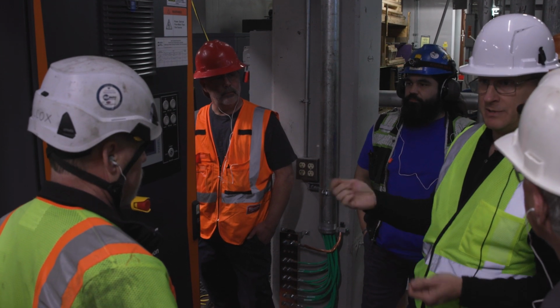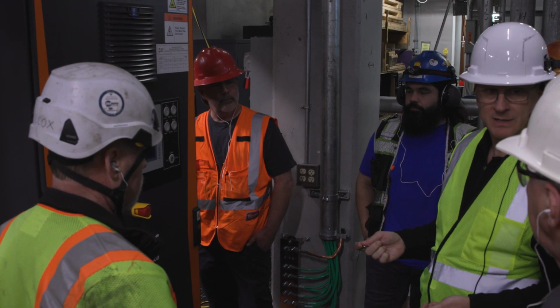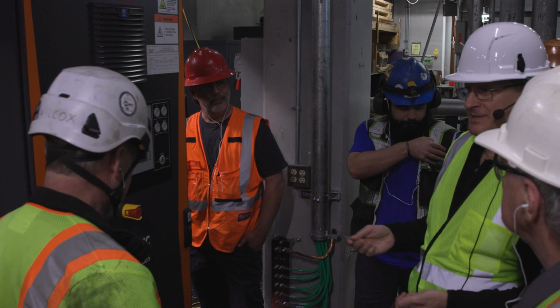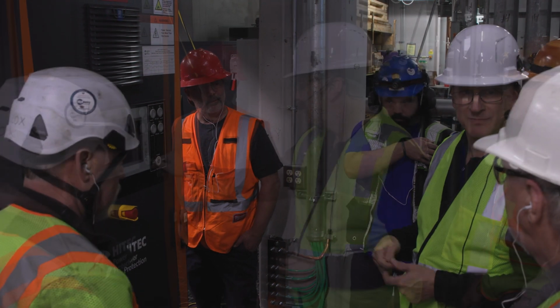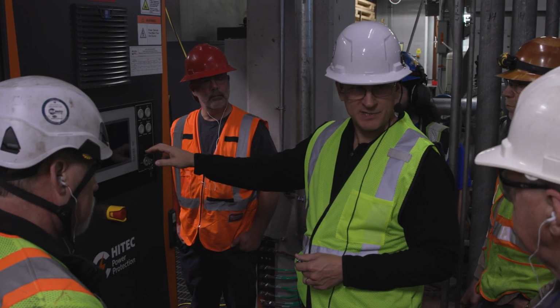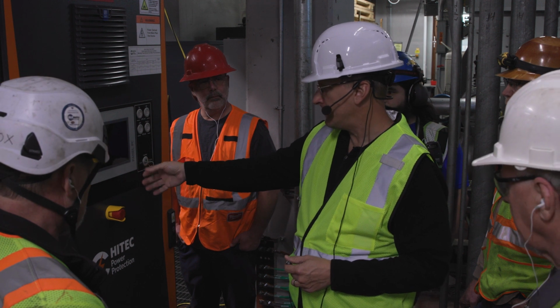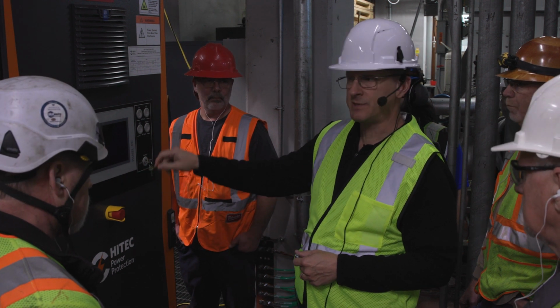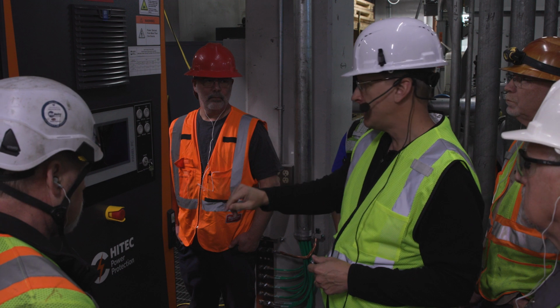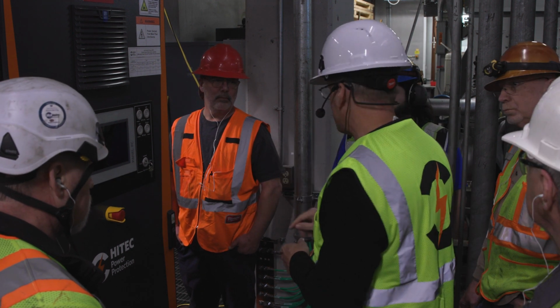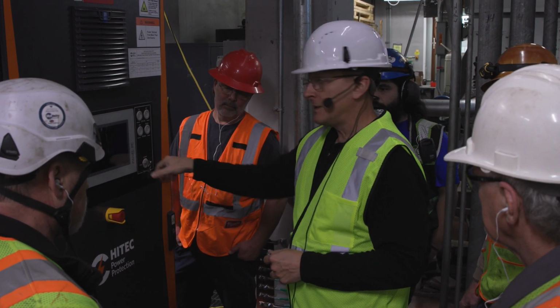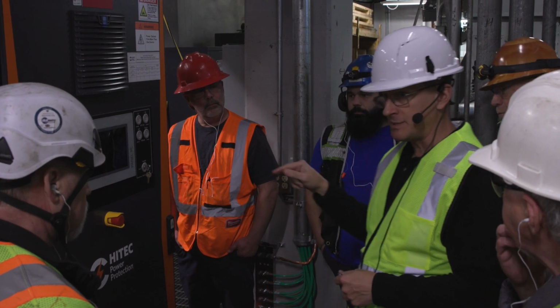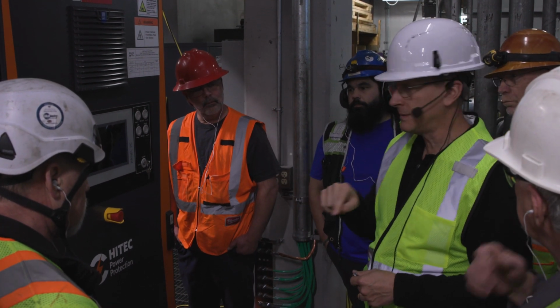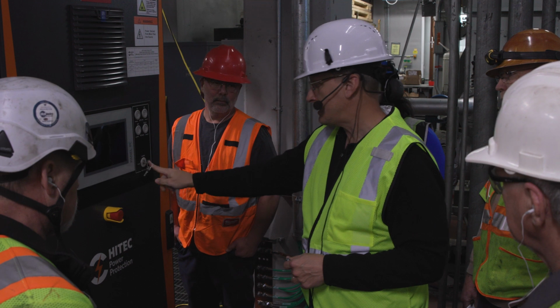This is your key. Keep it where you want to. Don't lose it, because otherwise you're not going to be able to operate the system. So if you want to operate the system in front of the panel, then you'd have the key in the local position. That's giving you local control at this HMI. There's a third position called SCADA. You actually have the ability to operate the system through the SCADA system remotely, and you do that by putting it into the SCADA position.